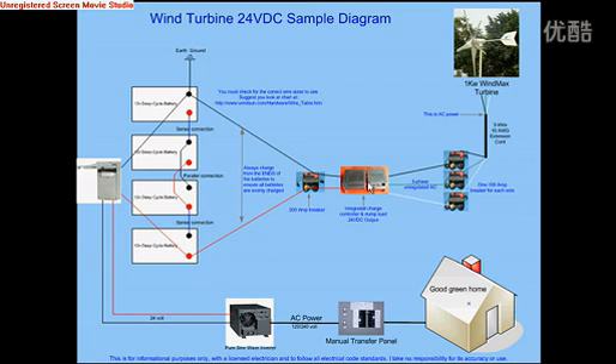So anyways, the power comes into here, and then from here it leaves as 24 volts DC, and you need to go through a 300 amp breaker, and then go to your battery bank. The power from the charge controller always needs to go to the extreme ends of the batteries. In other words, if you have more than one battery, then you should go from one positive, which is on one extreme end of the bank, to the negative that is furthest away. And that ensures that all the batteries in the middle are evenly charged.